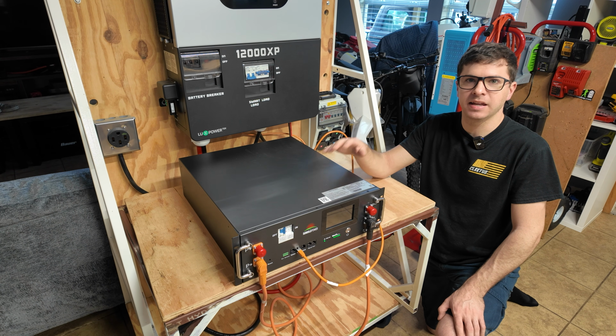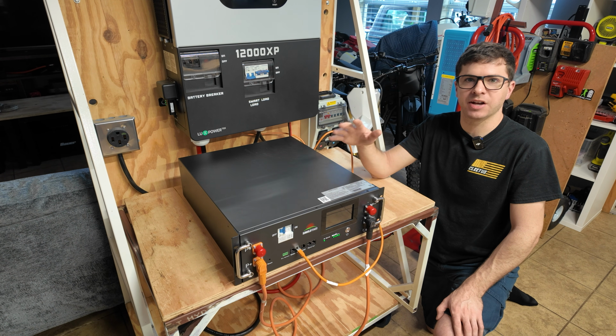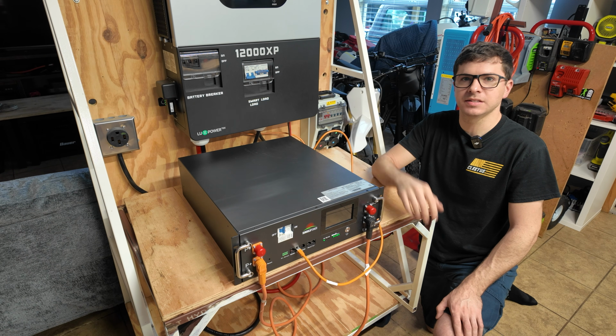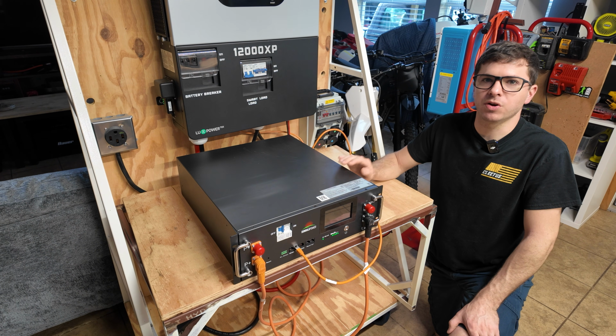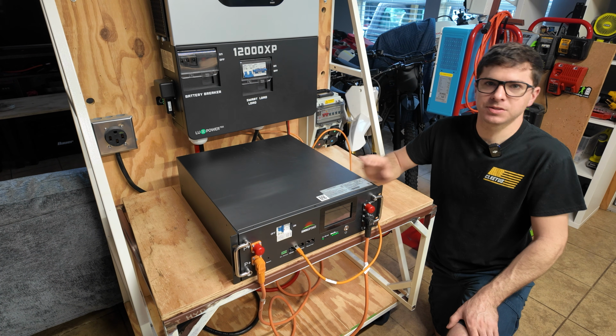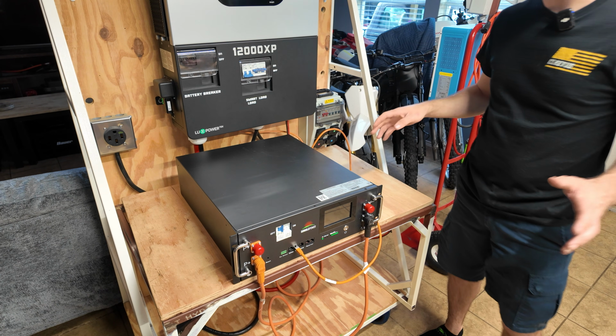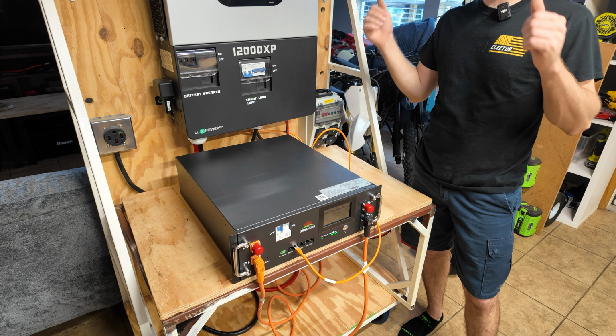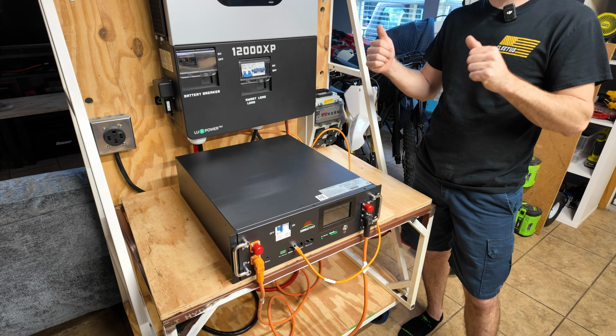I'm gonna run this thing at 80 amps and just kind of see how the battery performs, make sure nothing overheats. Keep in mind this battery is rated up to 100 amps of discharge continuous, so running it at 80 amps should not be a problem. The only reason I'm gonna run it at 80 amps is because it appears the inverter is gonna limit the discharge to 80 amps.